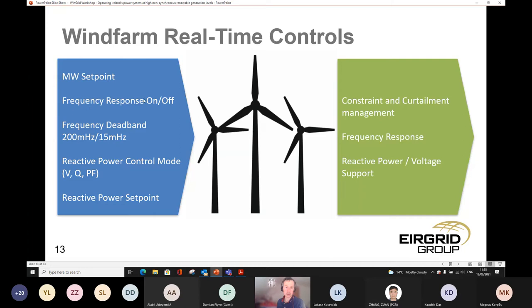We can turn frequency response in the wind farms on and off. We can select either a wide or narrow frequency dead band on the wind farms. For transmission connected wind farms, we can set their reactive power control mode from voltage control, a pure reactive power set point control, or power factor control. And then we can actually set the voltage, Q, or power factor set point on the wind farms.